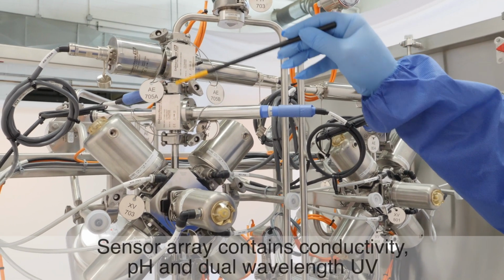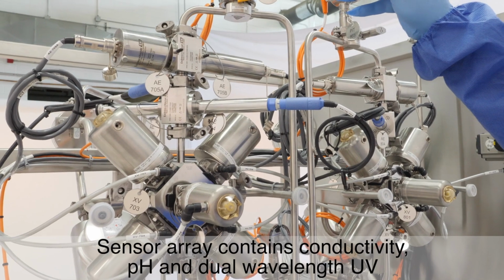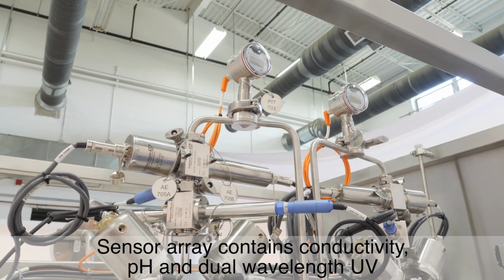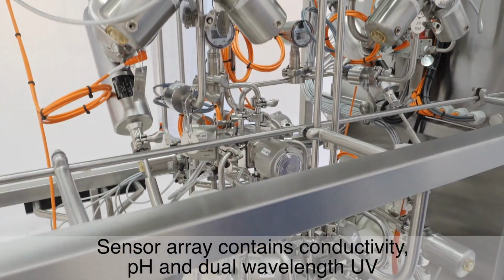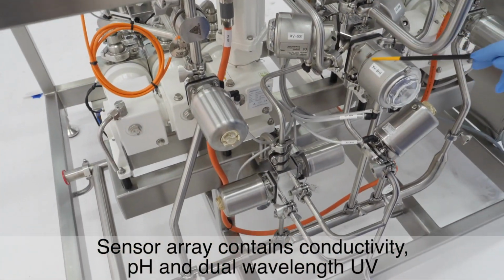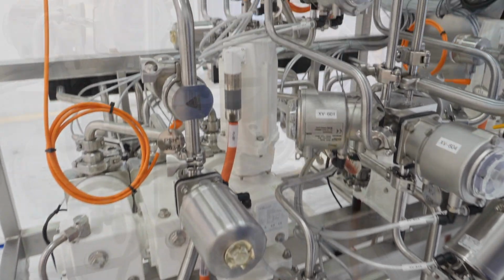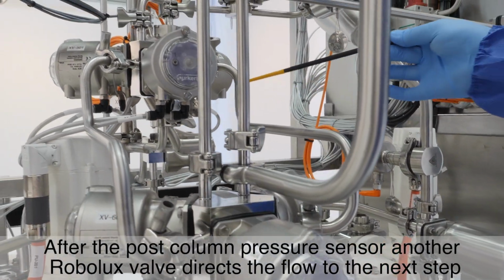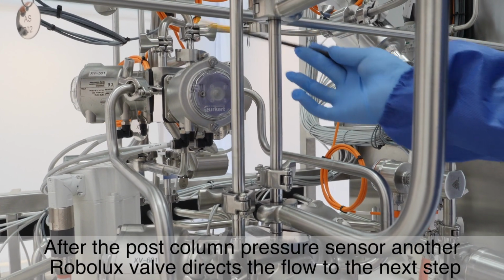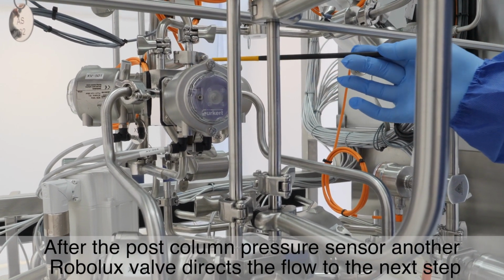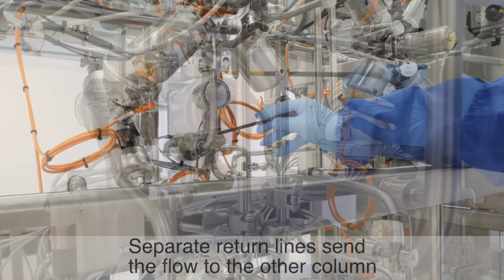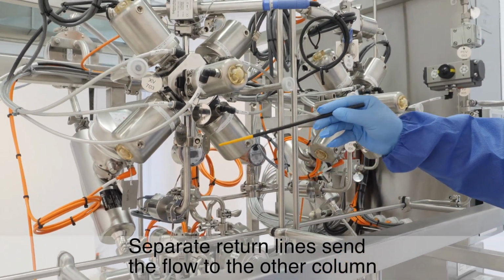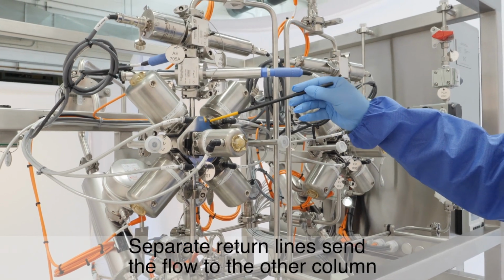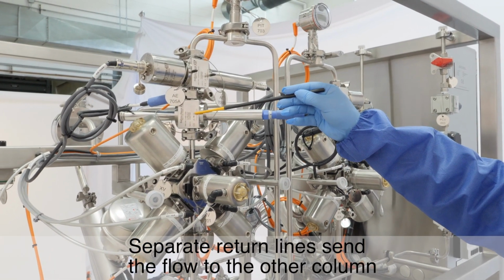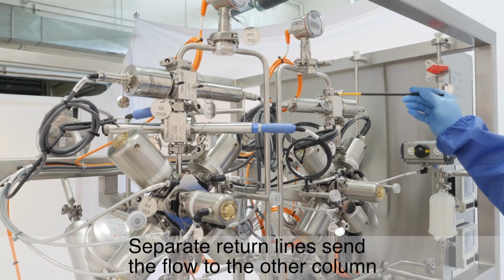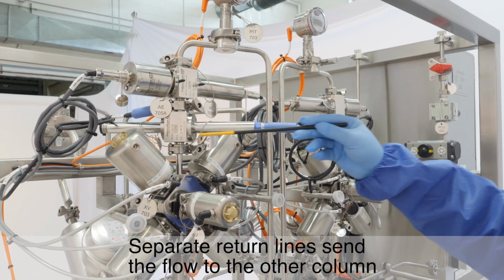Leaving the column, one finds a sensor array, which is comprised of conductivity, pH, and a dual wavelength UV detector. The flow passes the column outlet pressure gauge before entering the second Robolux valve, where the flow is sent to either the outlets or back to the first Robolux valve. In this example, the flow is directed back into the first Robolux valve. There are two separate return lines, one connecting column 1 to column 2, and the second for connecting column 2 to column 1. Depending which column is in the first position, one of the two return lines is used.